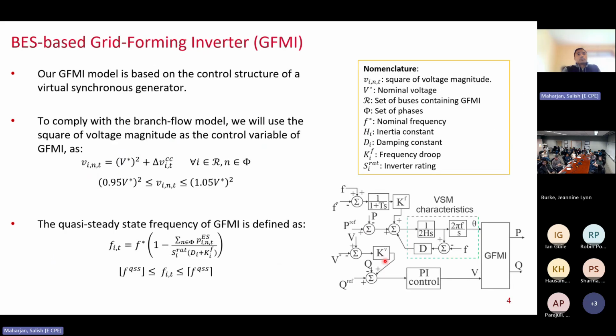Okay, so let's talk about grid forming inverters, which are powered by battery energy storage. We are considering virtual synchronous generator control based grid forming inverters. For the virtual synchronous control, the overall diagram of the control is shown on the right hand side here. So basically, VSM tries to mimic the characteristics of a synchronous generator. That's why this kind of grid forming inverter is parameterized with an inertia constant and damping constant. They have a frequency droop constant as well as a voltage droop constant. So the overall control is to regulate voltage and frequency while delivering some active and reactive power output.